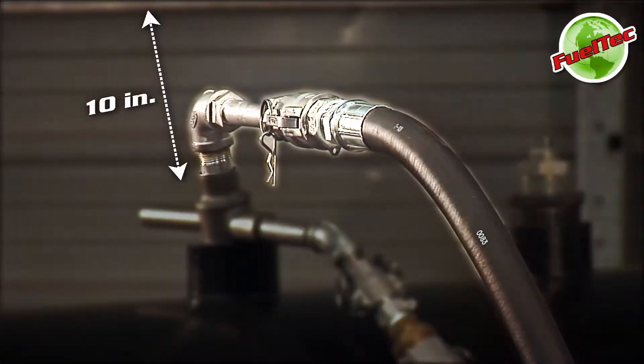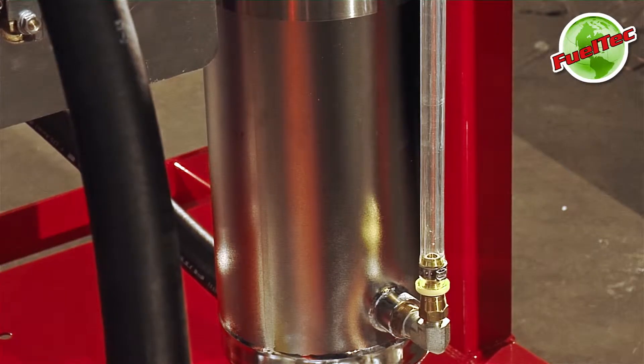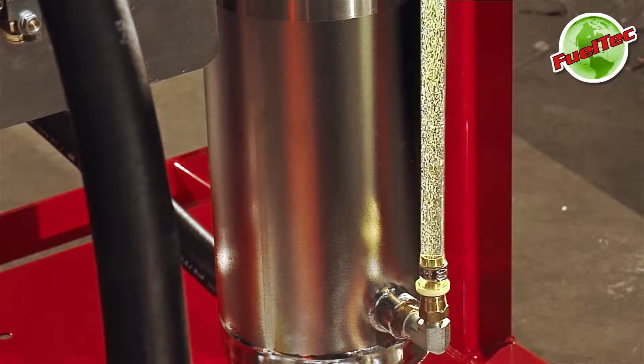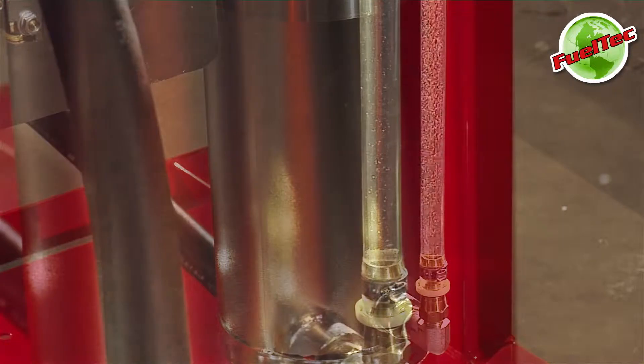Raise the pickup tube 10 inches above the tank bottom and turn on the switch. Observe the sight tube as the fuel level rises. Make sure to notice the fuel color. When the sight tube is full of fuel, lower the pickup tube to the tank bottom to begin removing water.